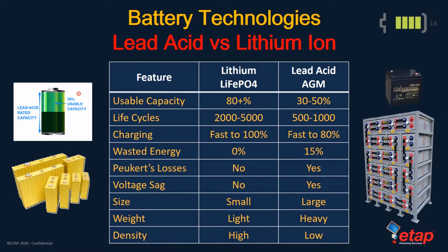The final 20% of the lead acid battery capacity cannot be fast charged. The first 80% is usually bulk charged by a smart multi-stage charger, but then the absorption phase begins and the charging current drops off dramatically, making the last 20% a slow charge process or a trickle charge process. Lead acid batteries suffer yet another inefficiency issue: they waste as much as 15% of the energy you put into them due to the inherent charging inefficiencies. So if you provide 100 amp hours of power into a lead acid battery, you're actually only storing 85 amp hours effectively.